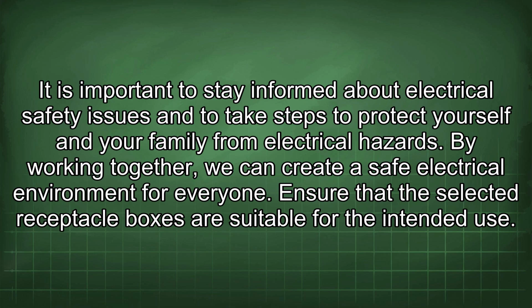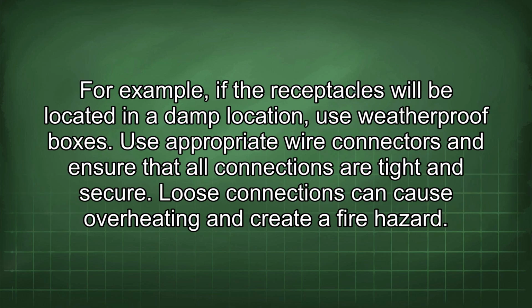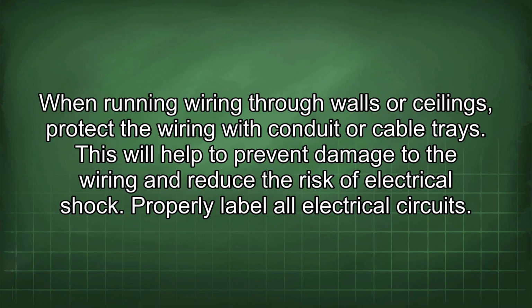Ensure that the selected receptacle boxes are suitable for the intended use. For example, if the receptacles will be located in a damp location, use weatherproof boxes. Use appropriate wire connectors and ensure that all connections are tight and secure. Loose connections can cause overheating and create a fire hazard. When running wiring through walls or ceilings, protect the wiring with conduit or cable trays. This will help to prevent damage to the wiring and reduce the risk of electrical shock.